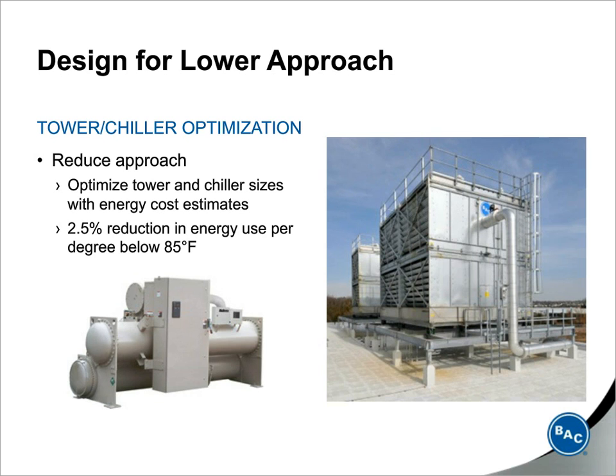The first design method that I want to review is designing for a lower condenser water approach. Now, when you design a system with a water-cooled chiller, it's very important to understand how operating costs are going to contribute to the total cost of ownership. It's a very significant cost of the entire system. So since the chiller consumes by far the greatest amount of energy in a water-cooled system, any increase you can provide in chiller efficiency can really offer the greatest return for your investment. And just to highlight this, a water-cooled chiller uses about 2.5% less energy for each degree below 85 degrees that enters the chiller. So now I'm going to define approach and explain how you can achieve greater efficiency.